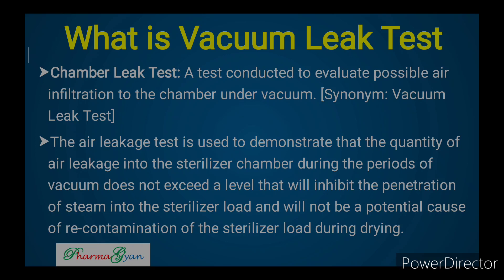Vacuum leak test checks the integrity of the chamber — you have to apply vacuum to a predefined level and hold it for some time. If the vacuum pressure is decreasing, it means there is a leak in the chamber — somewhere from the gaskets or different connections, air is entering inside. This is why we perform the vacuum leak test.